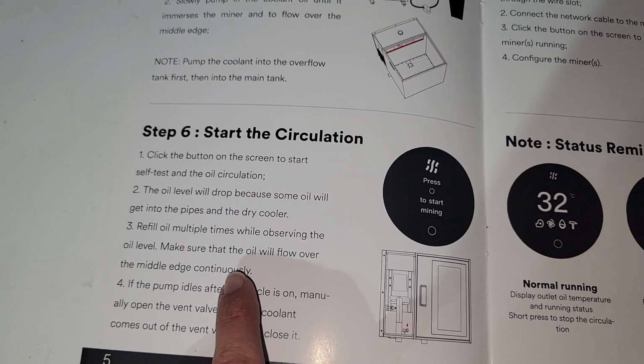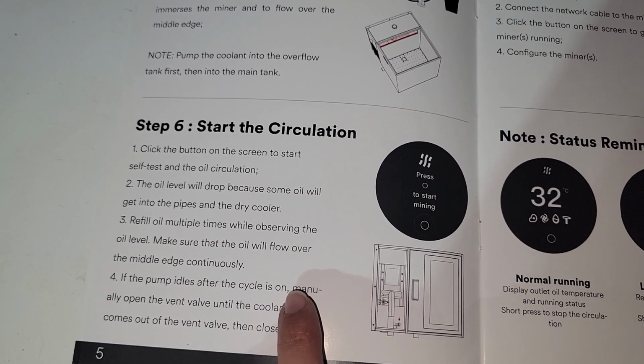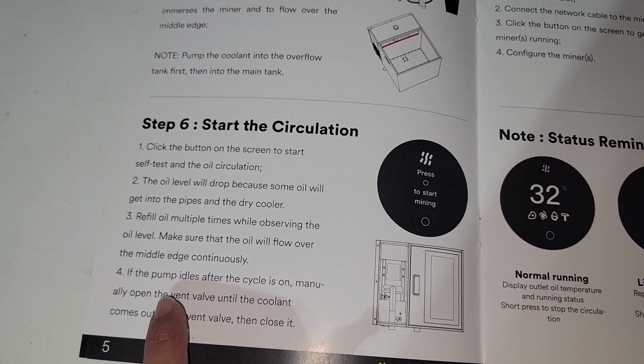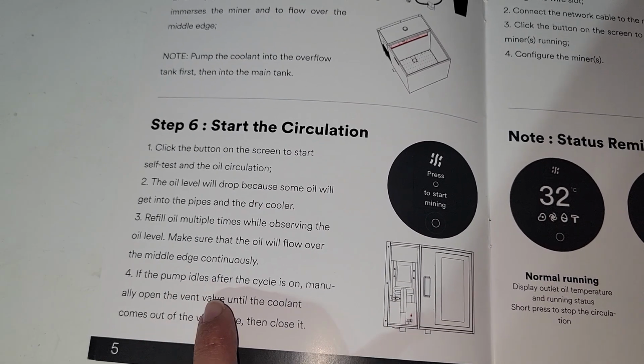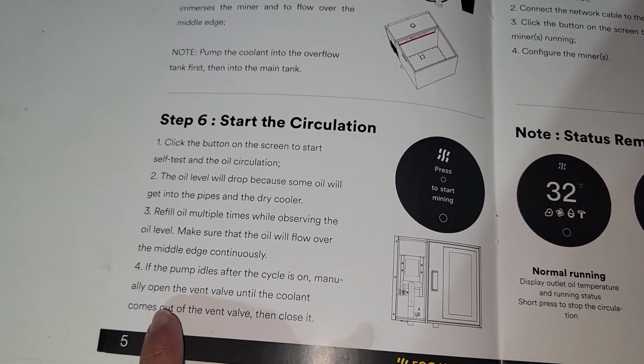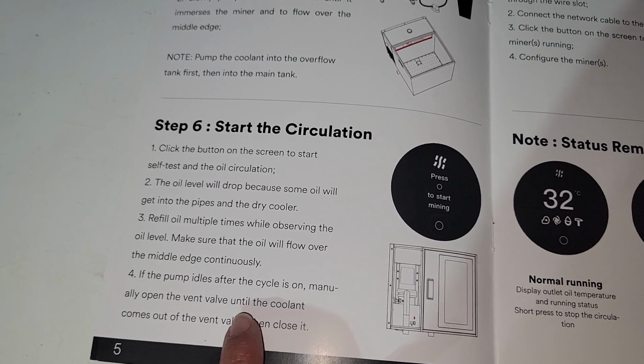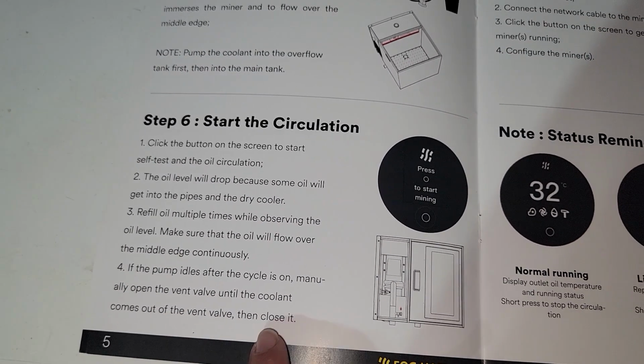We need to top it off, so we're going to flip the switch on the PDU, flip it off to make sure everything is good to go. Top it off. If the pump idles after the cycle is on, manually open the vent valve until the coolant comes out of the vent valve, then close it.